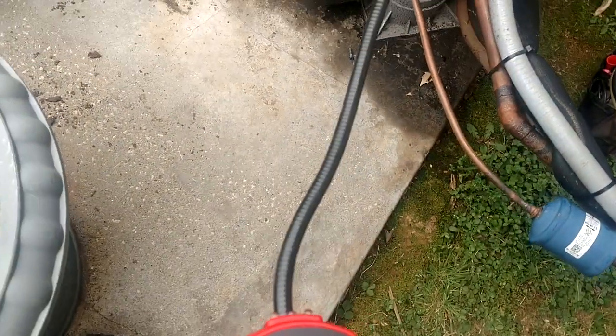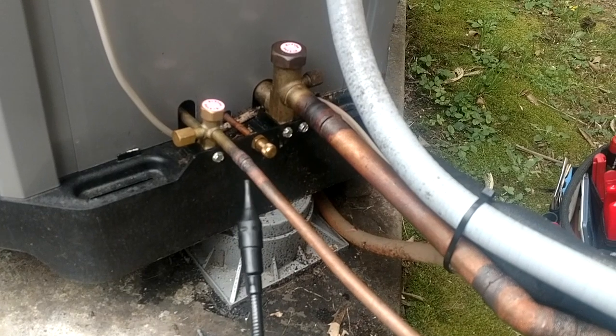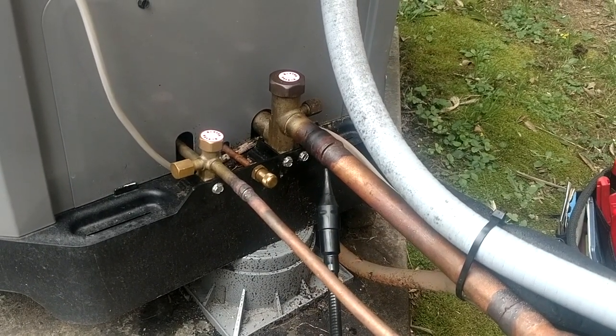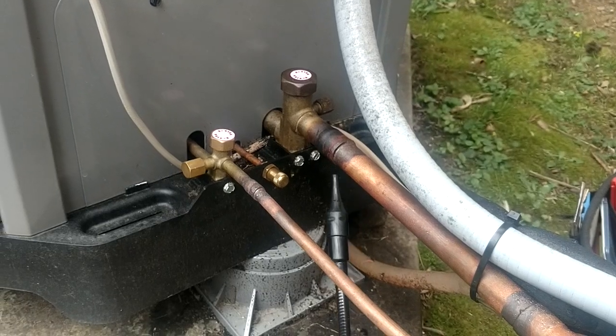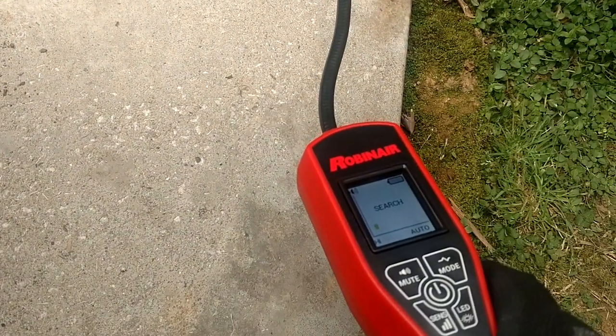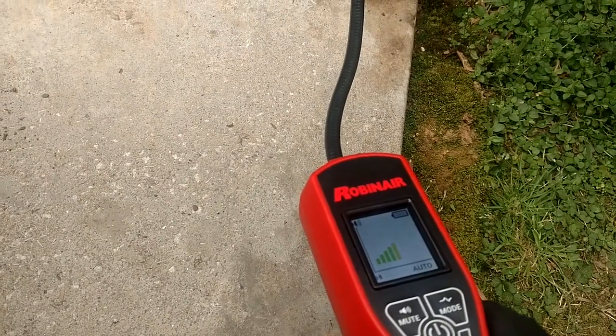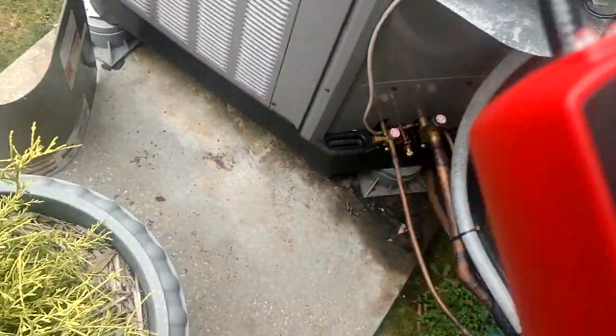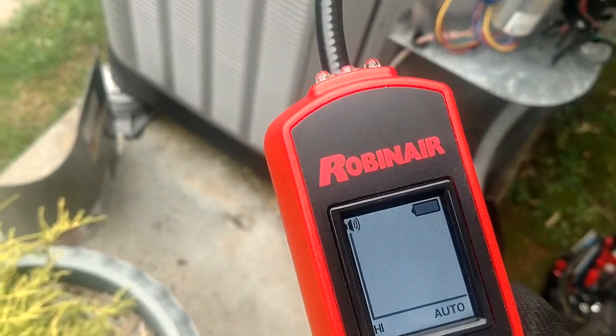We've got the Robinair LD7 out here, and on the bottom at the solder joint you can see we're picking it up there. I'm going to show you the size of the leak on the screen — you can see we're going up into the yellow.